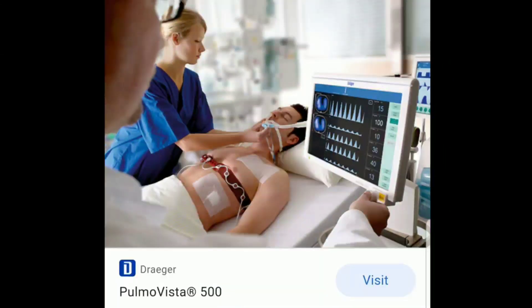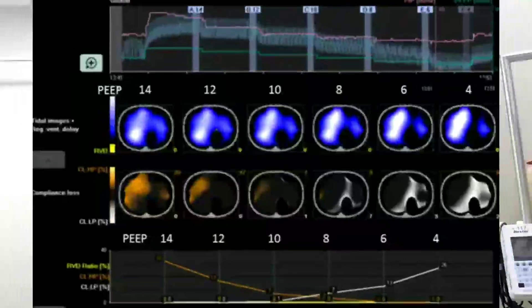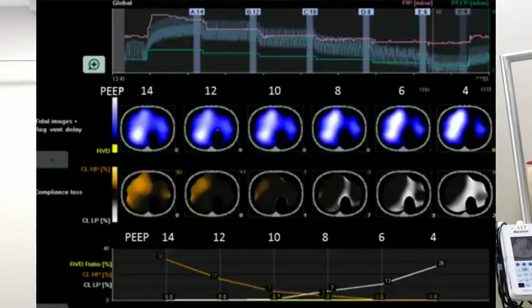Now we're doing PulmoVista, and with the PulmoVista we're able to set ideal PEEPs using electrical impedance tomography. Generally with my experience, most of the time, surprisingly, PEEPs are often eight or nine for optimal. The patients I find that sometimes have optimal PEEPs of six and eight are really those stiff fibrotic, non-recruitable lungs where the elastance is very high and the lung just snaps closed.